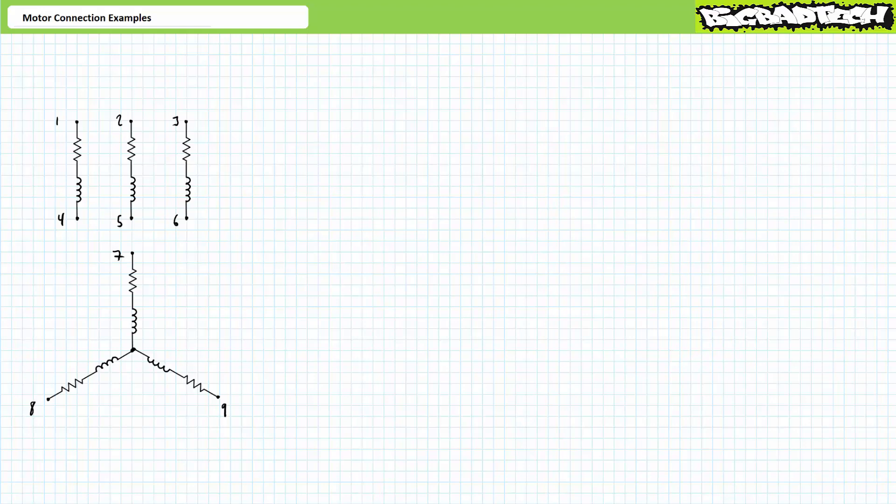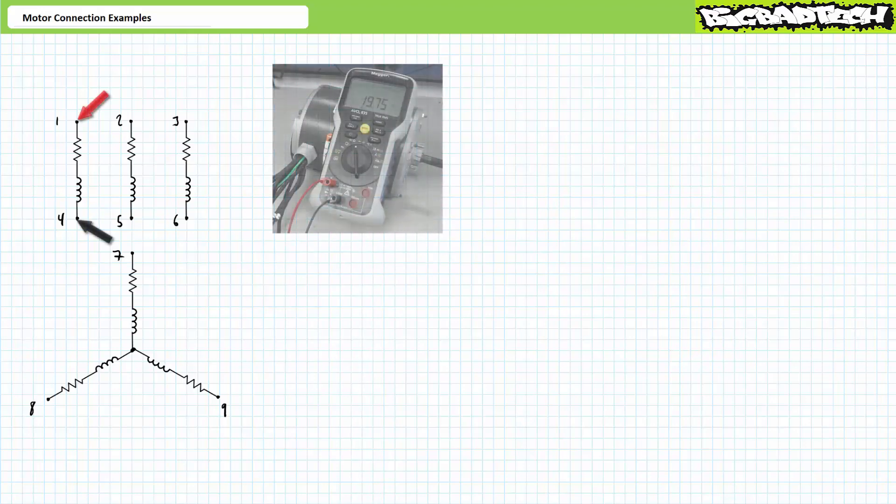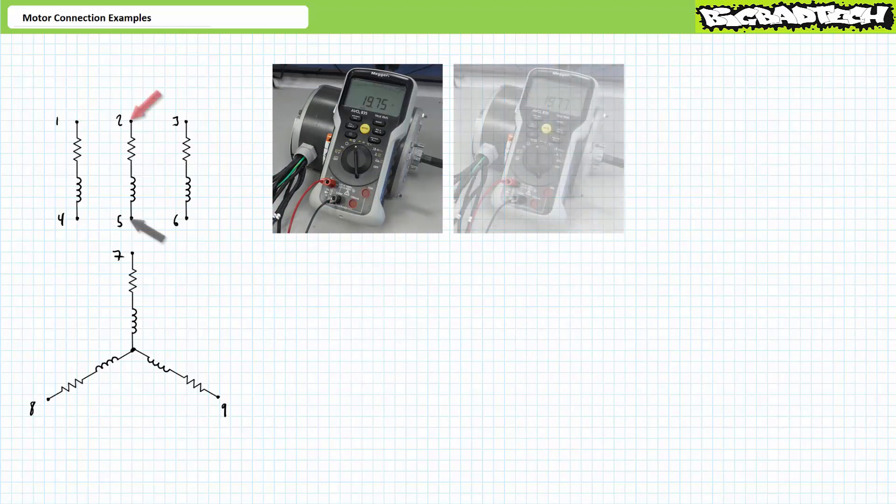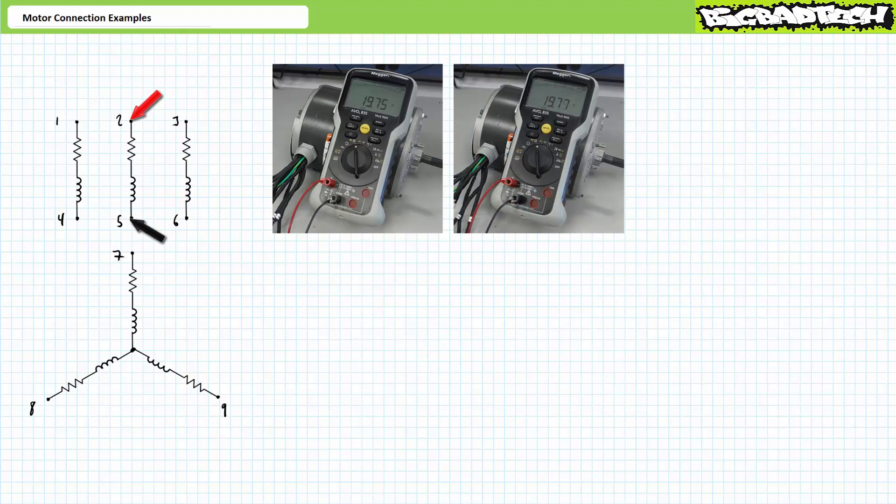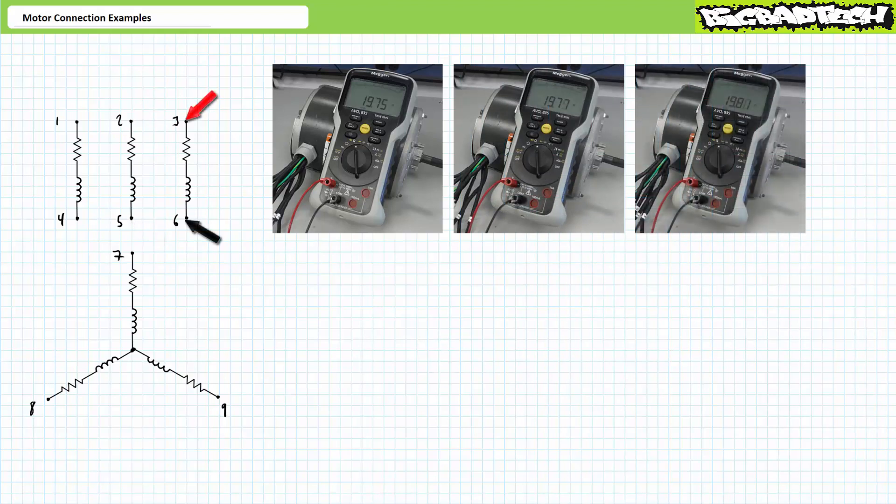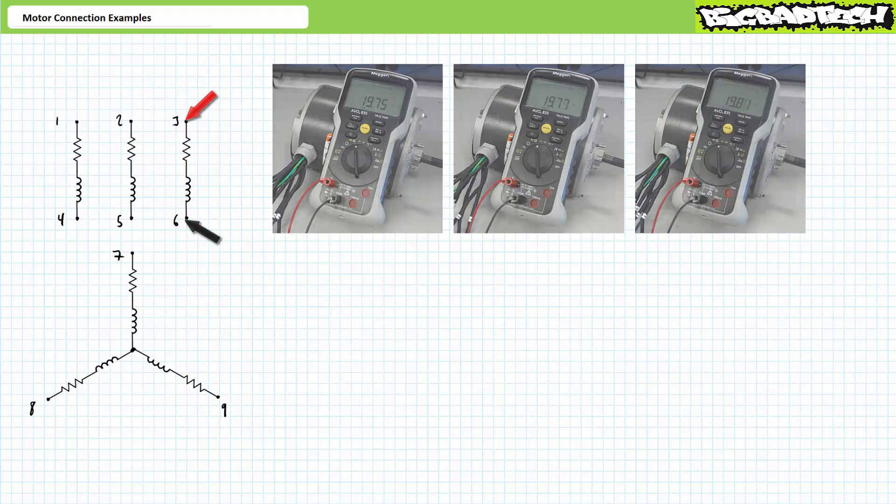Ordinarily three-phase AC motors are considered balanced loads and unless damaged each winding should theoretically have the same resistance. An ohmmeter demonstrates winding one-four has a resistance of roughly 20 ohms. Similarly, winding two-five also has a resistance of roughly 20 ohms. Finally, winding three-six also has a resistance of roughly 20 ohms. It looks like the isolated windings are indeed roughly identical.